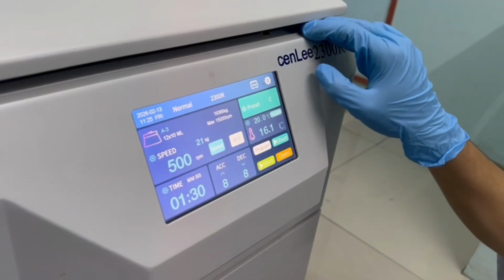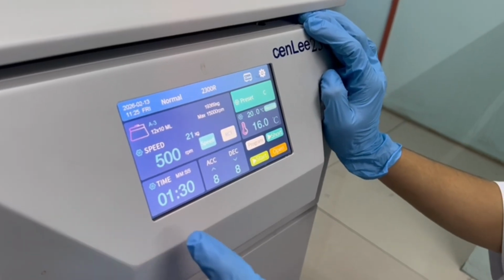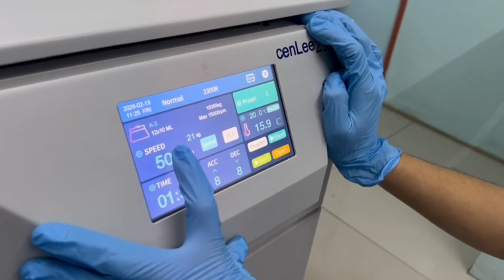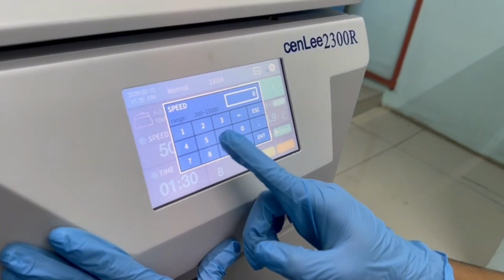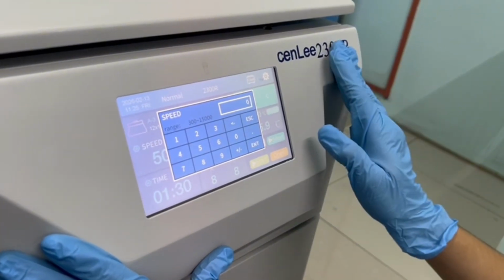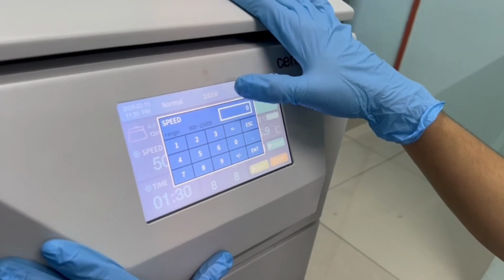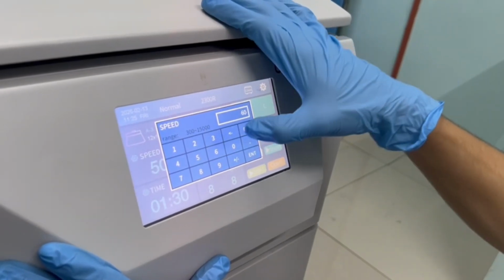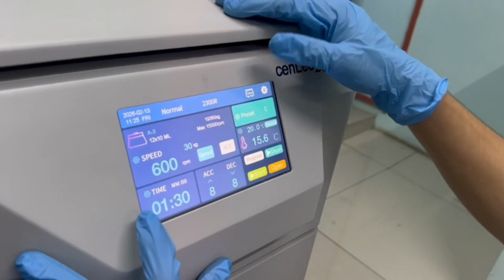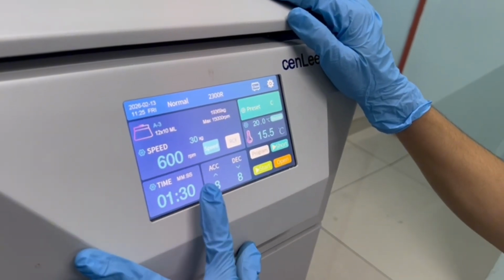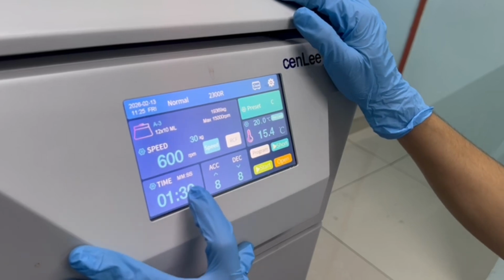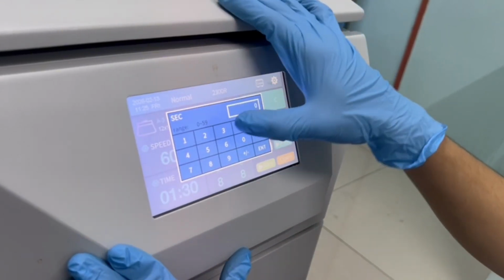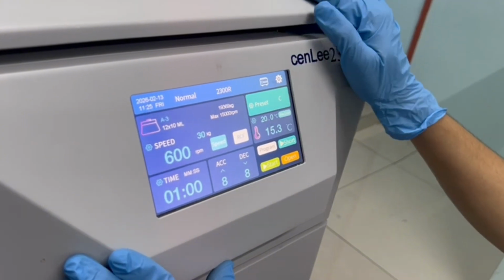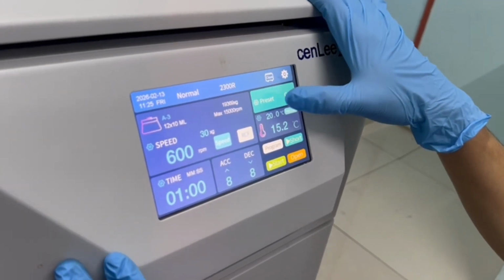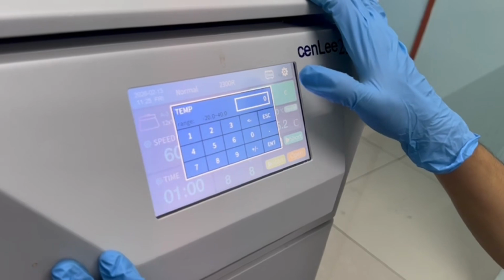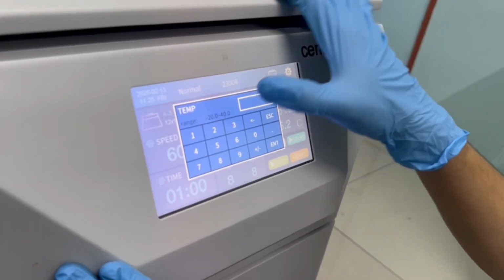Now we will demonstrate how to use the centrifuge. First, we will talk about speed. You can adjust the speed, how fast it goes. It can go from 300 to 15,000 RPMs, but we will only set it to 600. For time, we can set the minutes and the seconds, but for now, we will only set it to 1 minute, as you can see. And for the temperature, you can set it here. We will set it to 25.